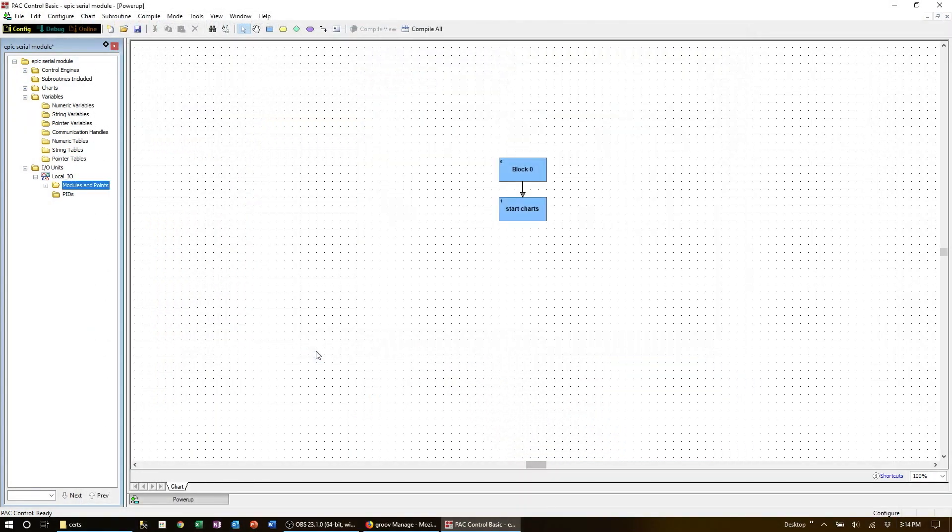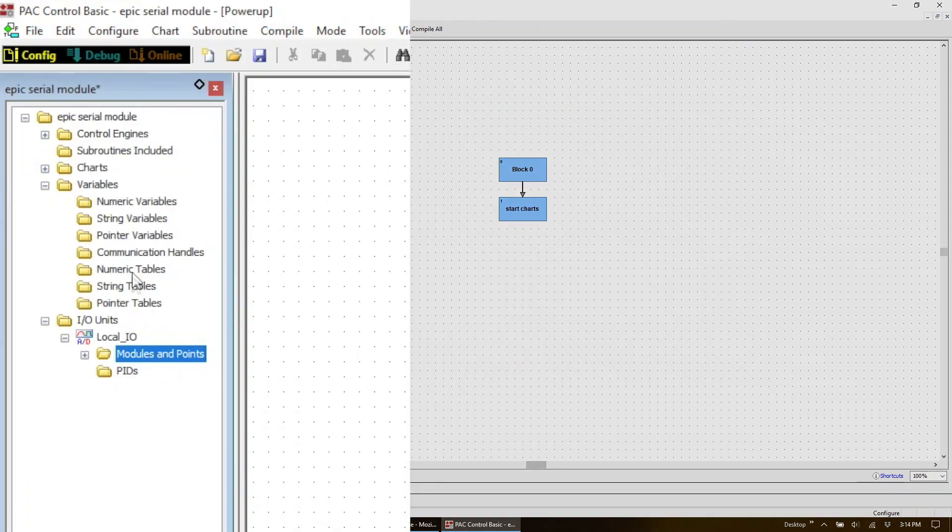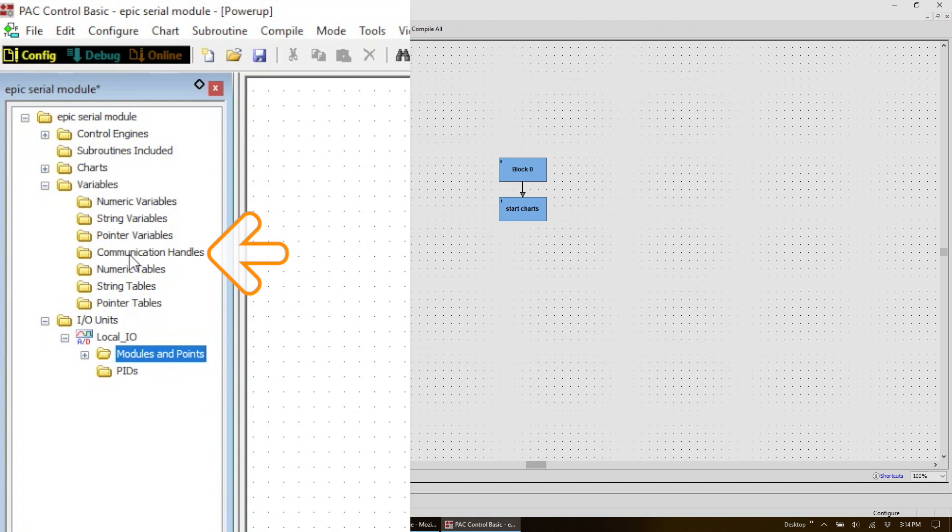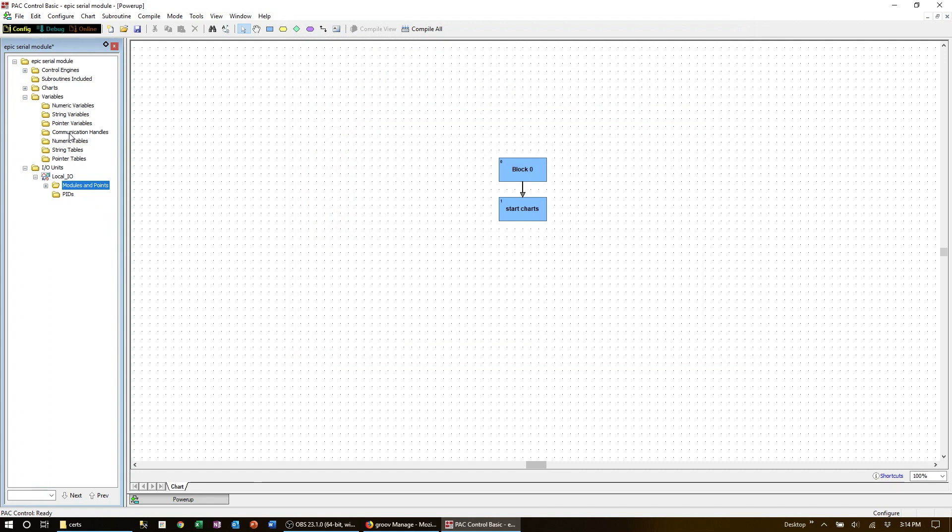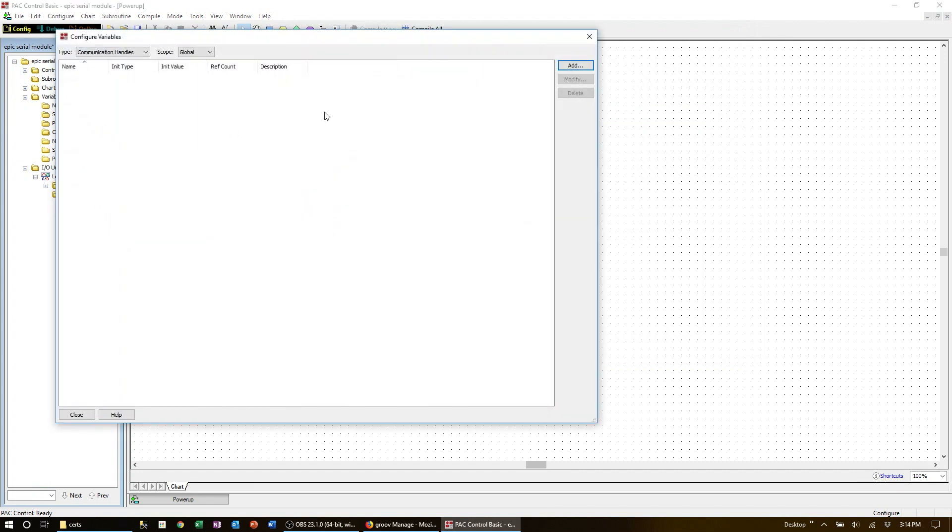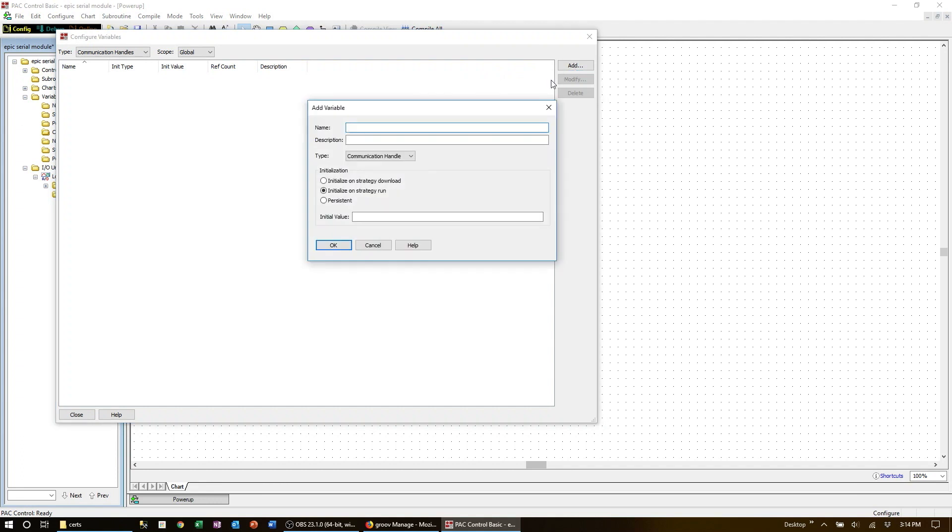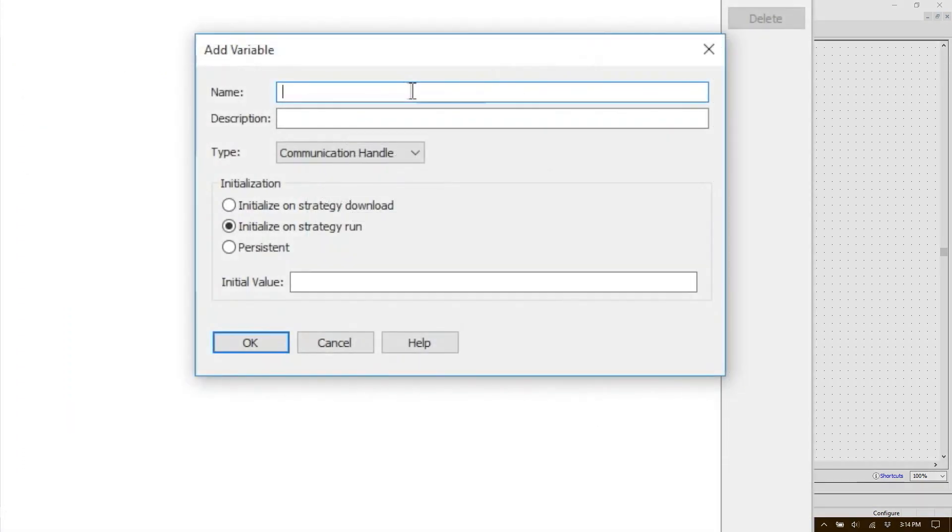Next we need to configure the baud rate, parity, data bits, and the stop bit. This is done as a communication handle variable that will be used to address the COM port in the software. Double click on the communication handle in the strategy tree and click on the add button. You could name this COM handle after the position on the rack or by the device or by some other naming convention. I'm going to name it CH for COM handle and then the name of the device, GPS module.